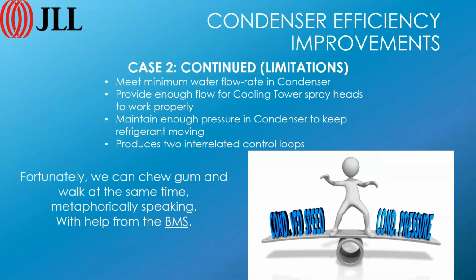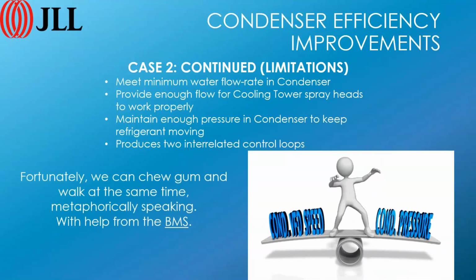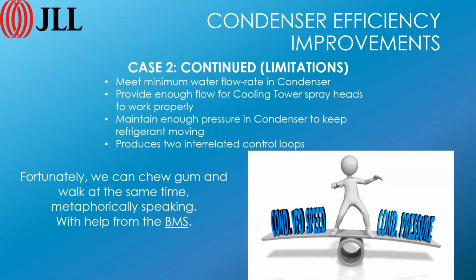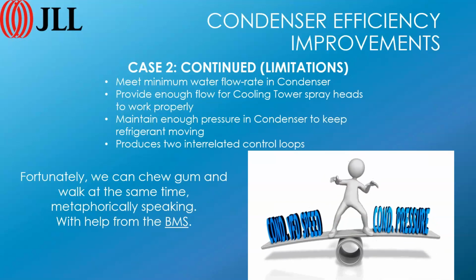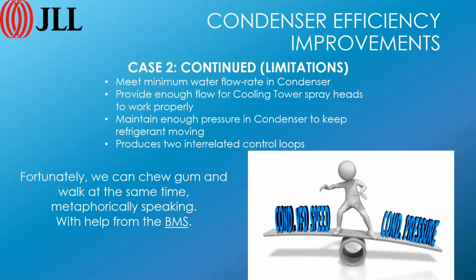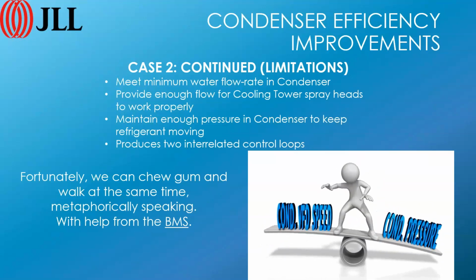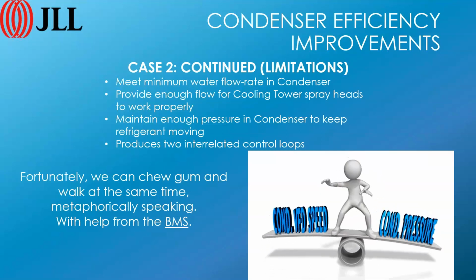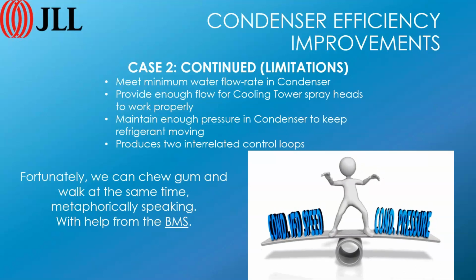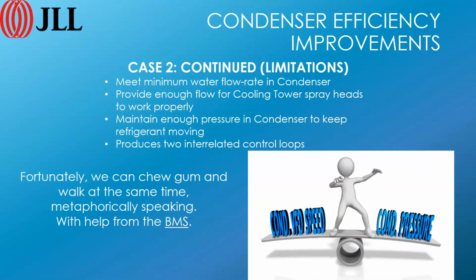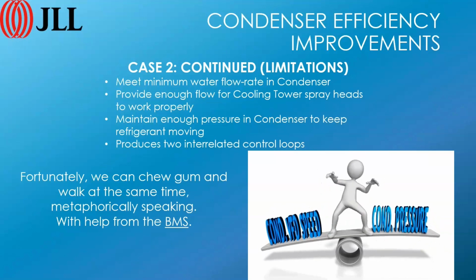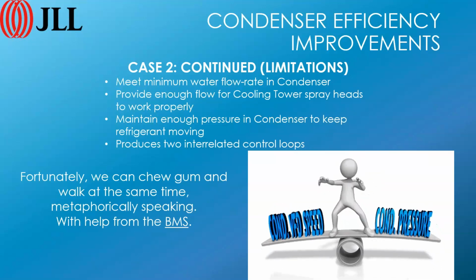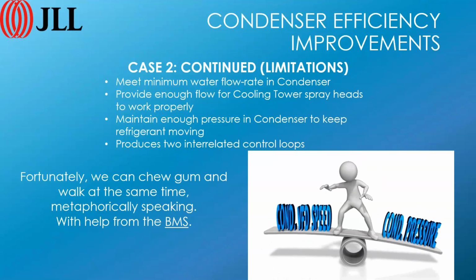There are some limitations. You have to have enough water flow going through the cooling tower for the dispersion nozzles or dispersion tray or spray heads to work properly. So in most cases, you can't really go below about 40% of max flow. And you have to have enough pressure in the condenser to keep refrigerant flowing. You also have to have enough water flow through the condenser to prevent sediment from occurring. Generally, you don't want to go below about 50%, maybe 40% is the low end, but around 50% is kind of a safer number.